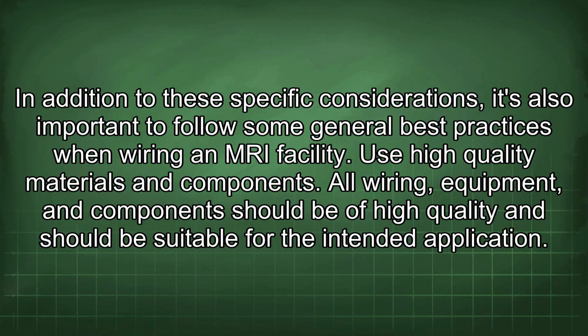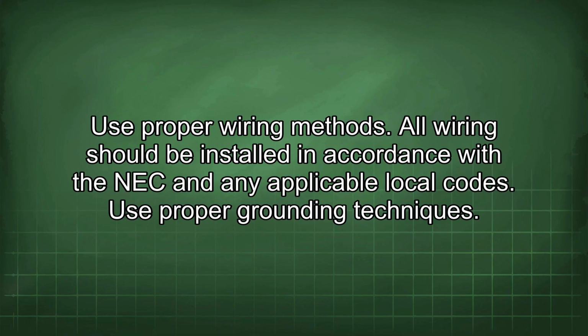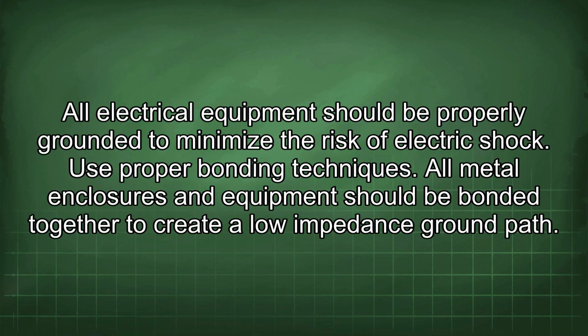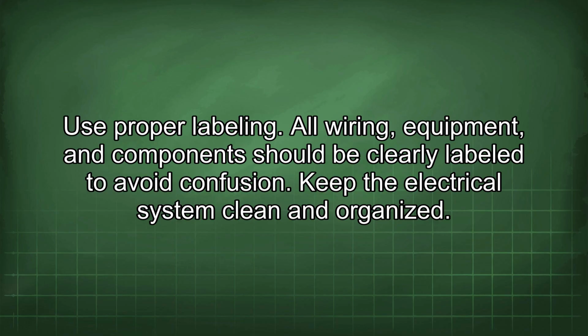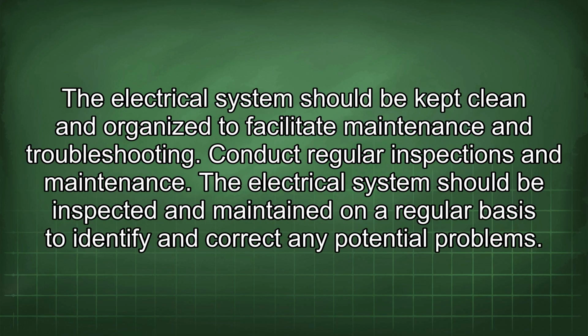facility. Use high-quality materials and components. All wiring, equipment, and components should be of high quality and should be suitable for the intended application. Use proper wiring methods. All wiring should be installed in accordance with the NEC and any applicable local codes. Use proper grounding techniques. All electrical equipment should be properly grounded to minimize the risk of electric shock. Use proper bonding techniques. All metal enclosures and equipment should be bonded together to create a low impedance ground path.